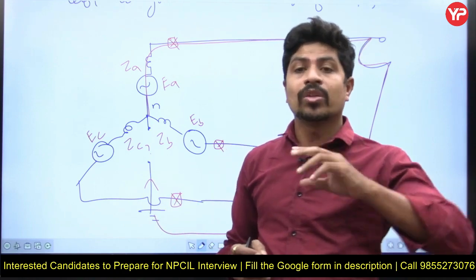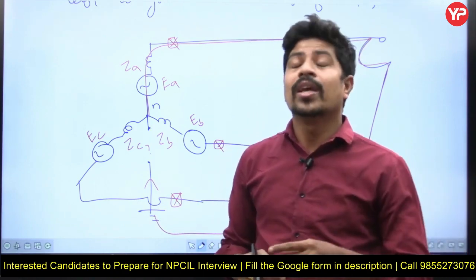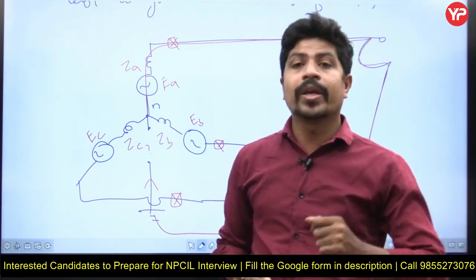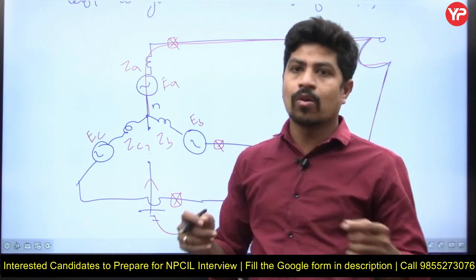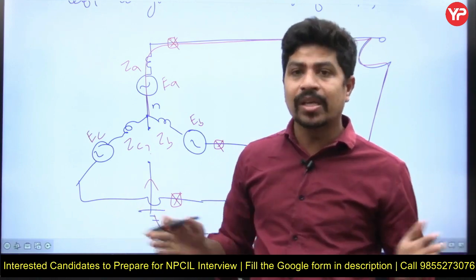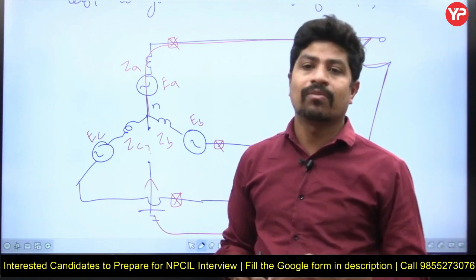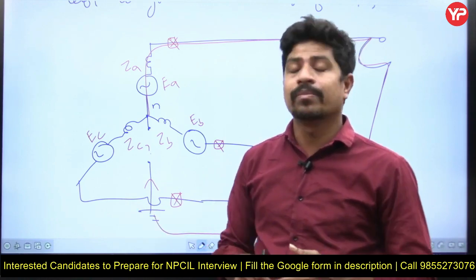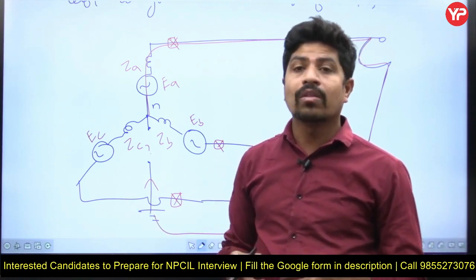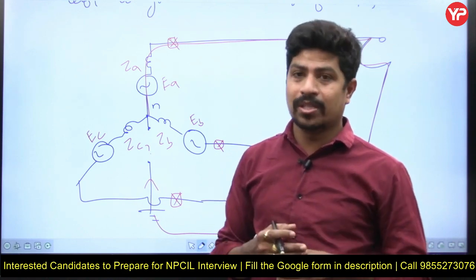If the relay is not in a position to recognize the present condition as a fault condition, it cannot give the trip signal to the circuit breaker. Therefore, the circuit breaker is not in a position to open its contacts, and the fault cannot be isolated from the existing system, right? Therefore, there must be a closed path. This is one of the disadvantages.